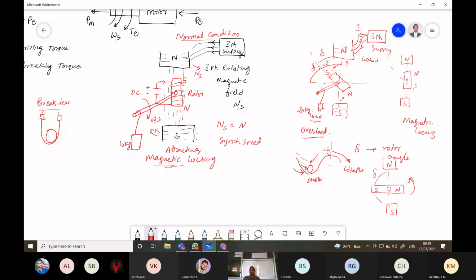So we are applying more load, more than the capacity of the machine, so the current also increases due to that. So if delta is more than 90 degrees, we are not achieving the stability. The rotor will not come back to its original position. It will not happen after it collapses. The same thing happens to motors also. Is it clear?